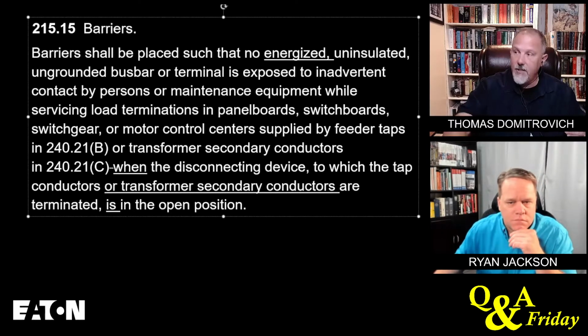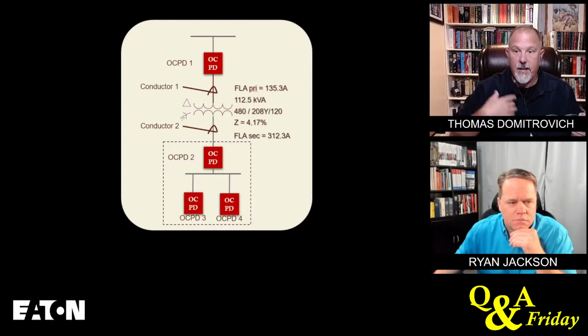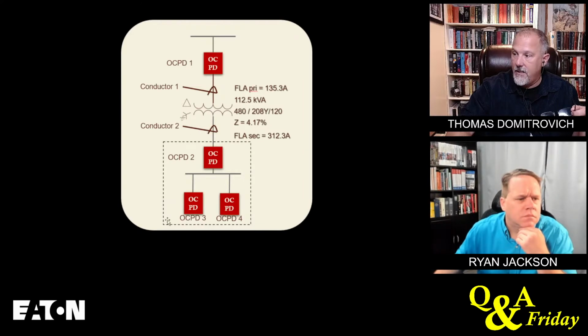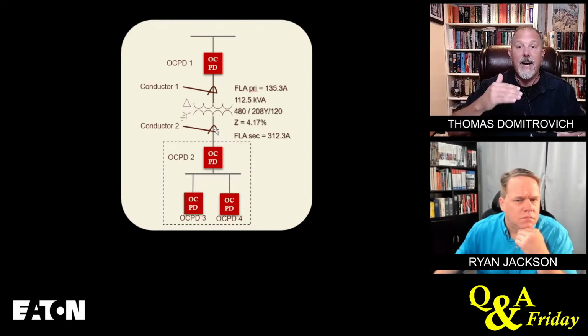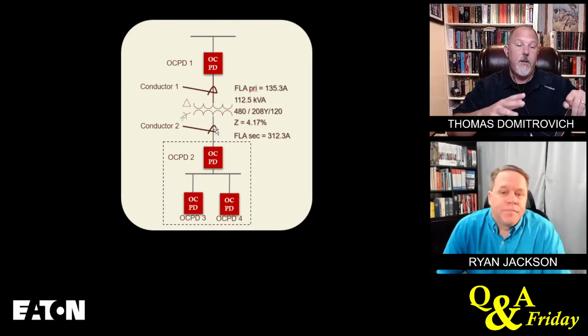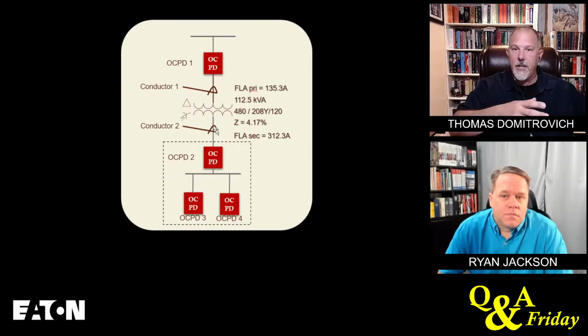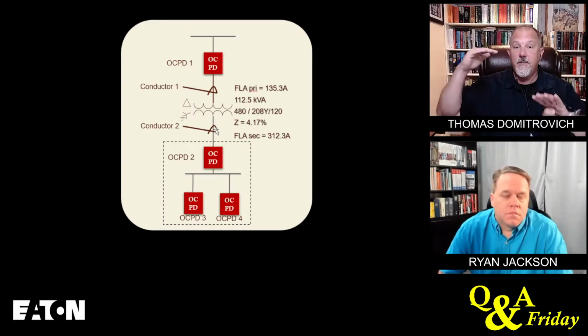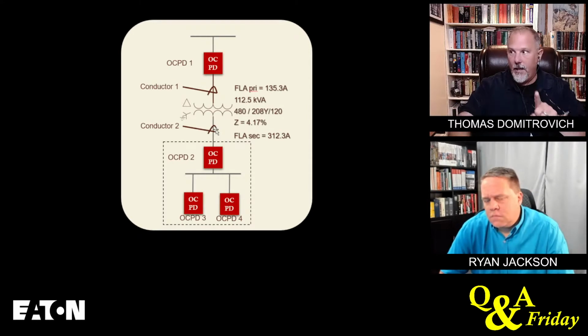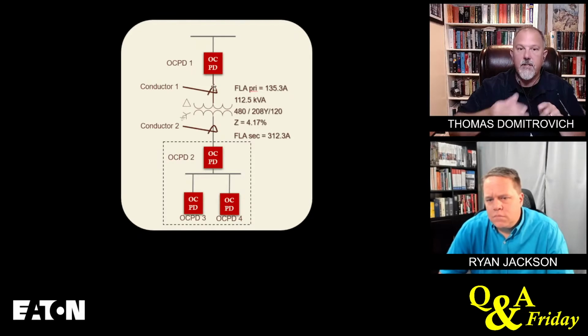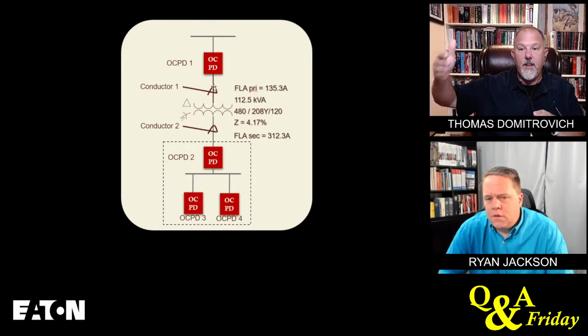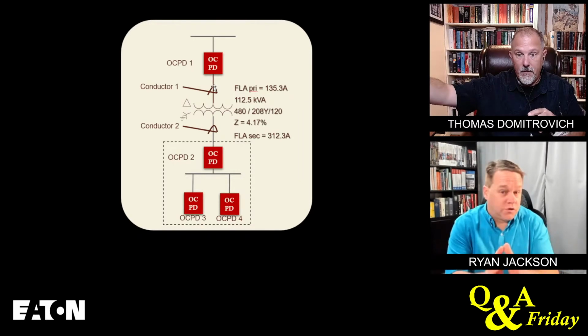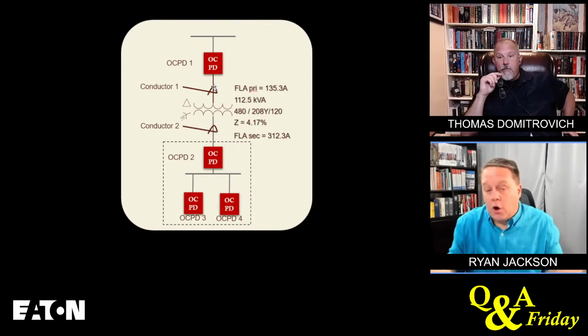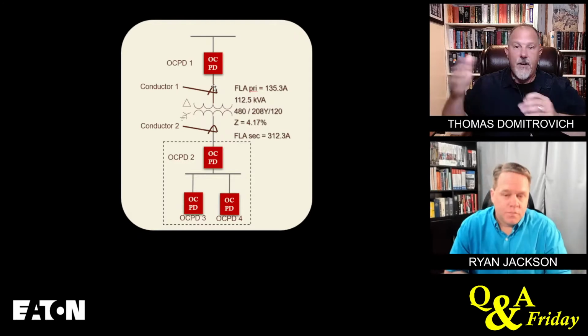But the challenge with a transformer, as you and I both know, is that this secondary piece of equipment usually has a higher, I'll call it risk, likelihood and severity. The likelihood is the same, whether it's a panel board on the secondary of a transformer or wherever that panel board's at. But the severity is higher only when I am selecting the primary overcurrent device with an inflated instantaneous pickup to ride through the inrush, right? To clarify, when you're talking about the risk and severity, you're talking about an arc flash, right? Yeah, the severity of an arc flash event, correct?